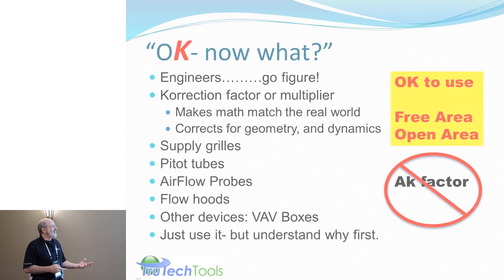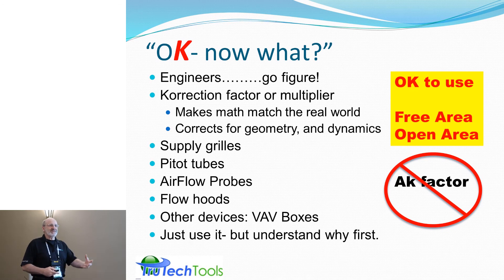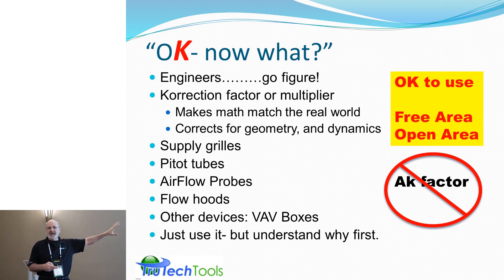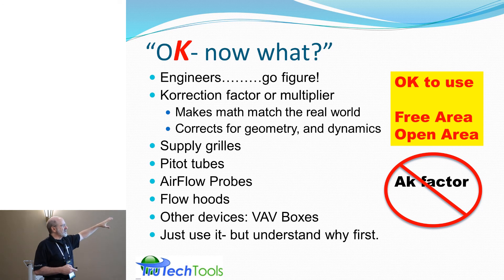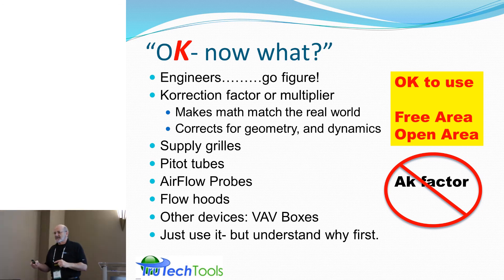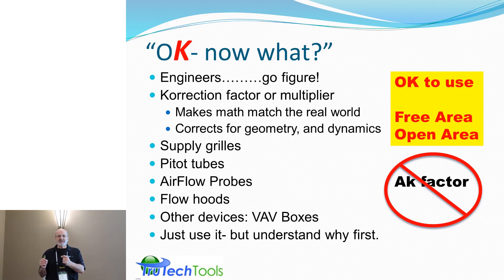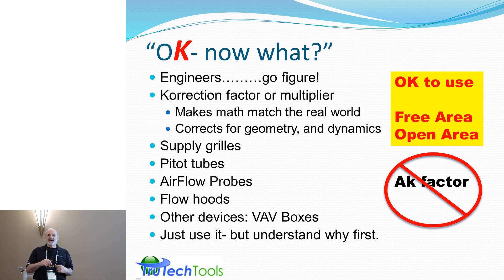Engineers made the world more complicated in their effort to make it better. The correction factor is a multiplier seen in many different places. Supply grills: it's okay to use the free area or open area factor, but AK factor is not a substitute — it relates to an old technique. Pitot tubes have K-factors — that's important to know. The Testo 510i displayless manometer, when you go into its app, lets you set the K-factor for the pitot tube. Most pitot tubes you purchase will likely have a K-factor of 1, but if it's different, you have to input it or you'll end up with a very different value.